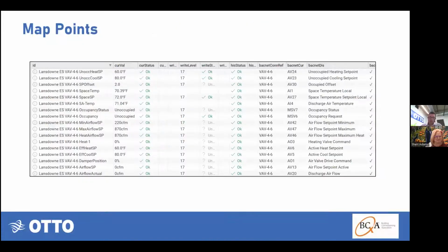Once we're connected, we're able to access all of the points associated with every controller. Just as an FYI, when we typically see a VAV box controller or any terminal unit, there could easily be 100 to 150 points that show up on the BACnet network. That's overwhelming—most people aren't aware of that. But again, we make it easy for you. We're essentially cherry-picking the points we think you want, and you're always welcome to add more or take them away. This is just an example here of what that point mapping looks like.